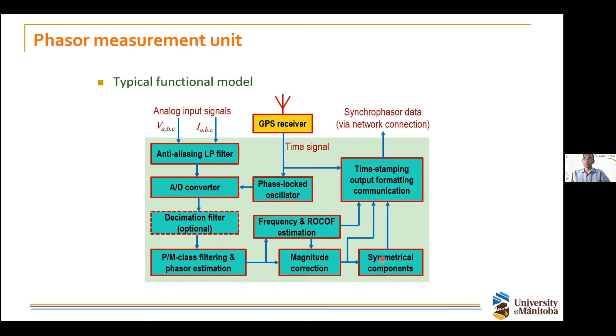And so I mentioned that it takes the analog measurements, but it could also be the sample data from IEC 61850 compatible merging units. Those are available in what they call digital substations. So instead of directly connecting analog signals, these merging units basically digitize the signal and then send the digital samples over network fiber optics to the relays. So you can use these sample values too.